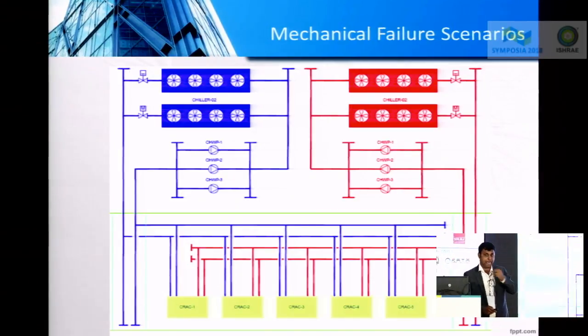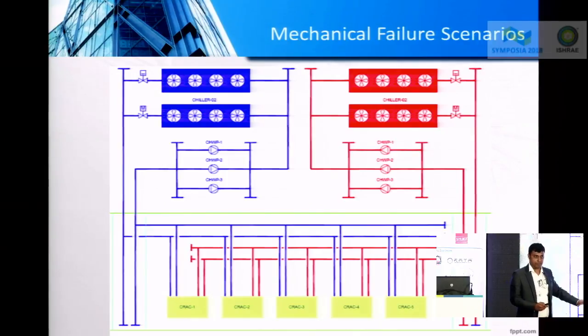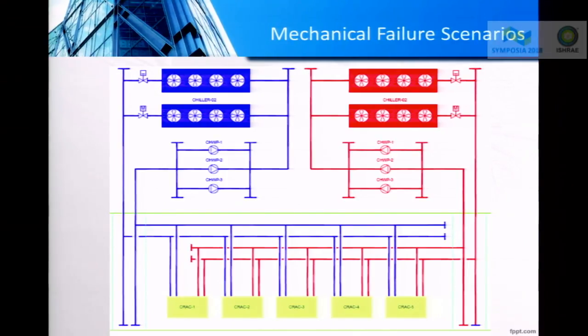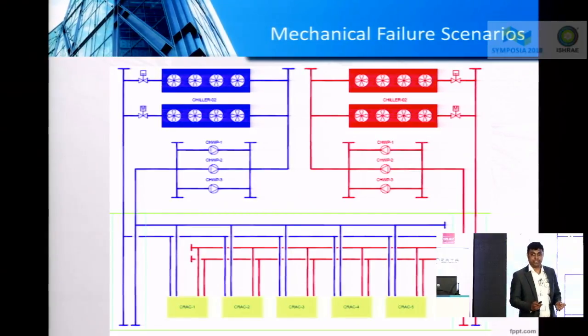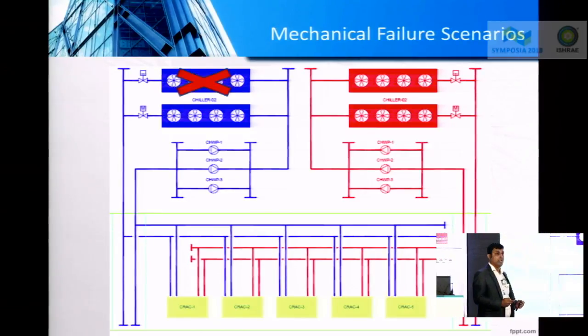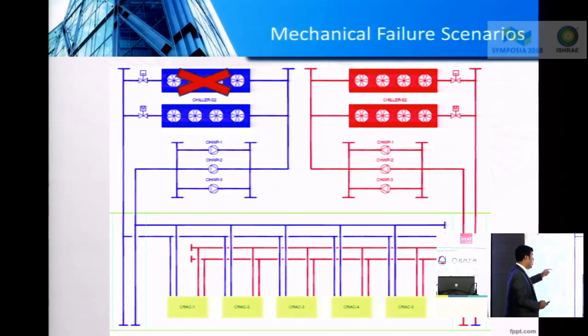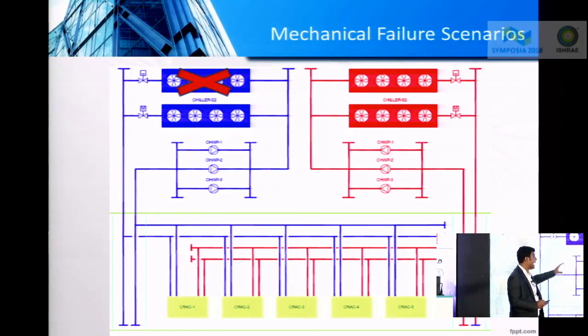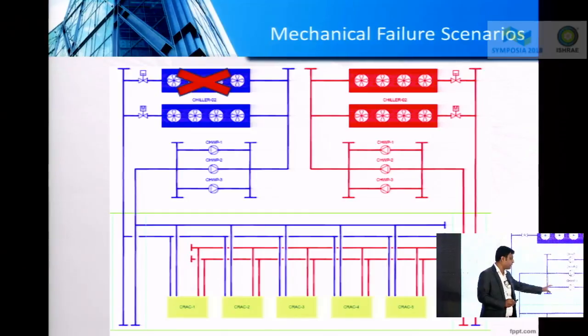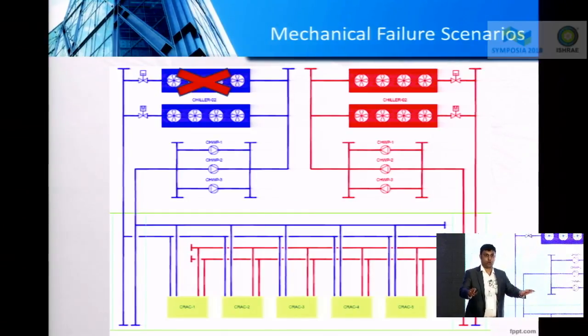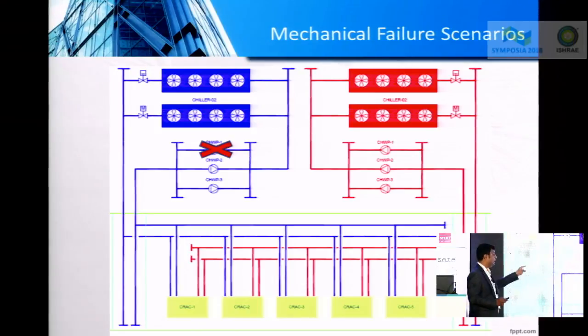Let's take an example. I have just created an example here. Let's say we have an N+N configuration. You have a source A system of chill water, and a source B system of chill water. And then you have CRAC units which are dual coil, fed by source A and source B. So how do I simulate these failures? The first thing I can do is fail the source A chiller and observe that the second chiller comes into the picture, there is no impact on the chill water supply temperature, and the temperature in the data hall is steady. I could also fail a pump and ensure that the standby pump comes into the picture. However, there is no impact on the chiller system.